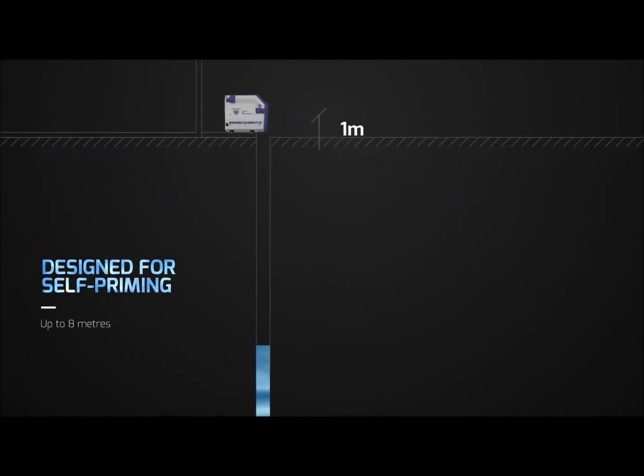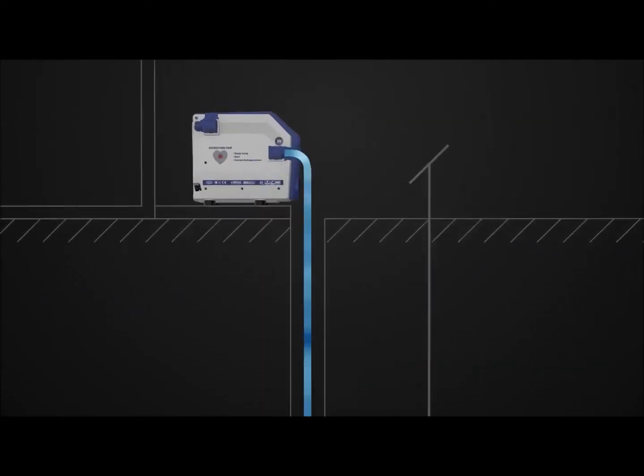DG-PED is designed for aspiration from wells thanks to its self-priming capability. To start it is enough to fill the pump. Open the top cap and vent cap and pour the water in. When the water comes out of the vent cap, the DG-PED can be started up. If instead you connect to the water mains, you only need to exclude self-priming.